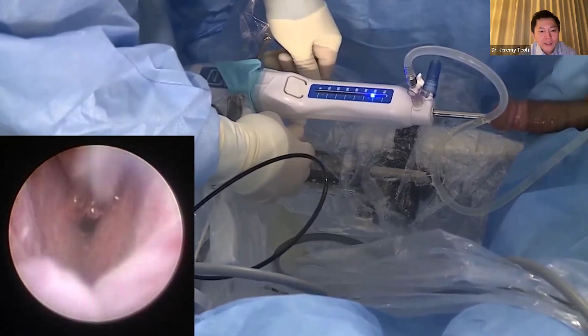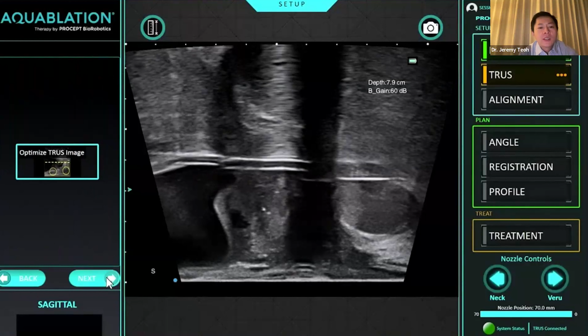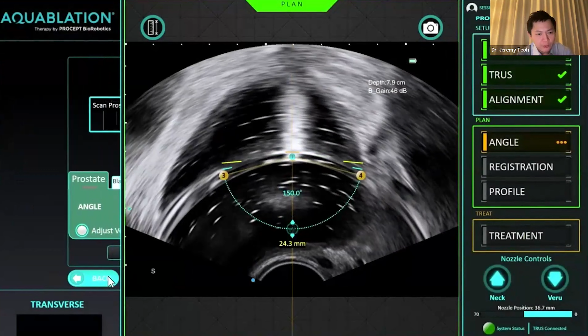And now we've fixed the device already, but we're rotating a knob. So you can see on the left, retract the scope until we just see the verumontanum. And my practice is actually to go back in a little bit in order to make sure that we're able to protect the verumontanum. Then we'll try to visualize the water jet, because we need to know where the water jet nozzle is. So we need to let the system understand where it is as well. You can see on top, there are two white lines there. This is the tip of the device as well as the water nozzle.